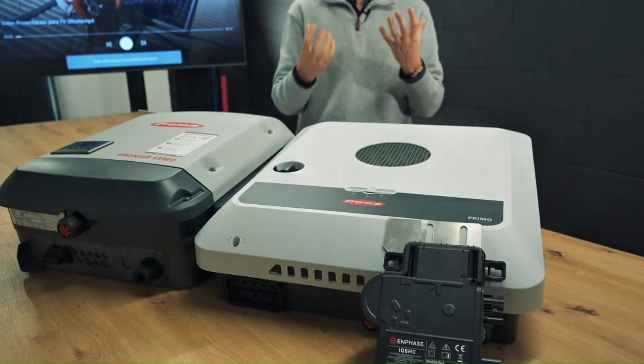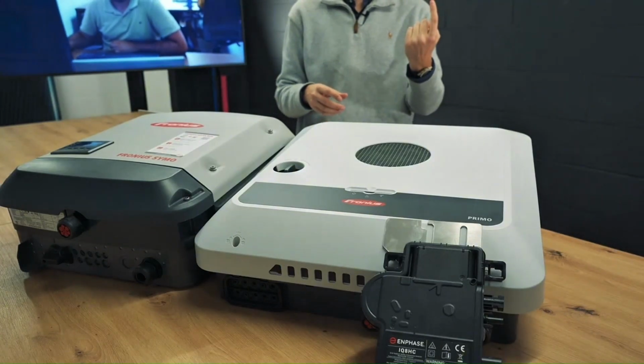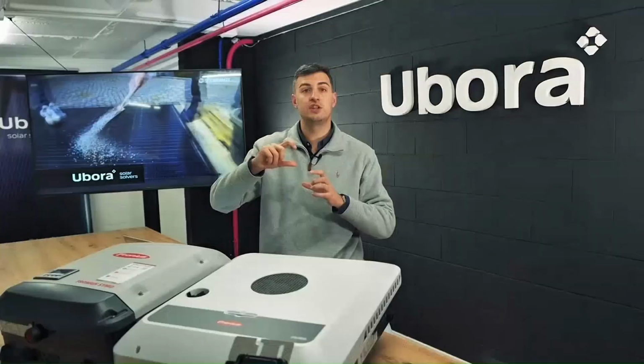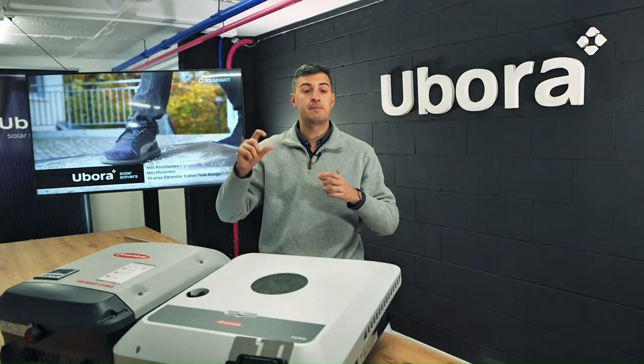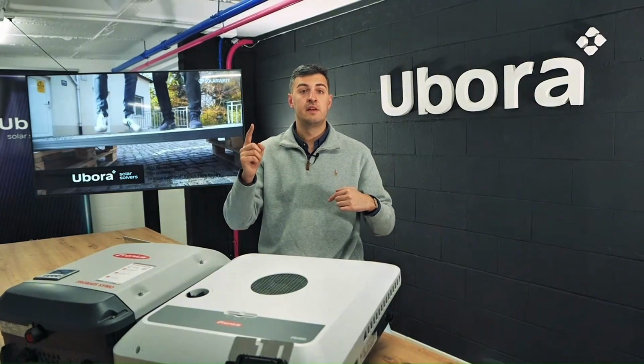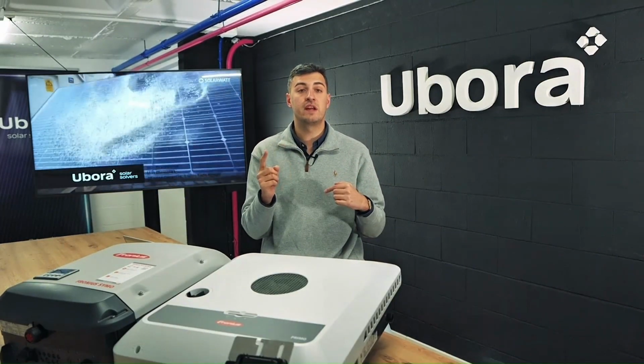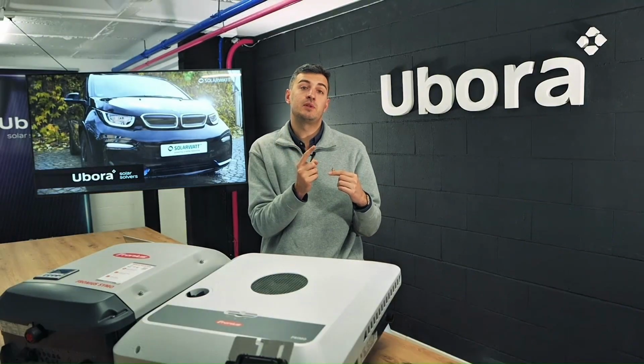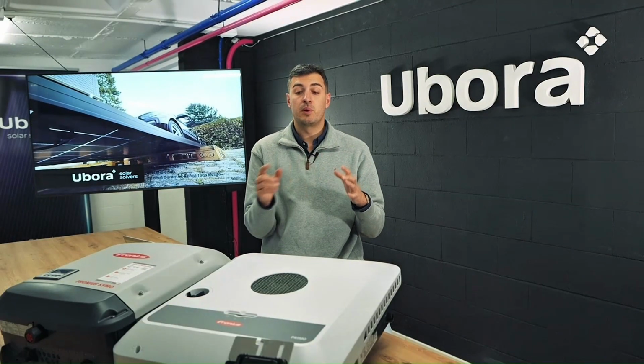Imagine that our inverter only had one input and we had two orientations, one east and the other west. In the morning, the panels on the east will have a higher voltage than those on the west. Then, if we connect them to a single MPPT input, we use that voltage, the MPPT control, to manage it to give us the maximum power point. What happens when you have two very different voltages, because the panels are producing very different voltages? The point of maximum power that we are going to generate will be lower.